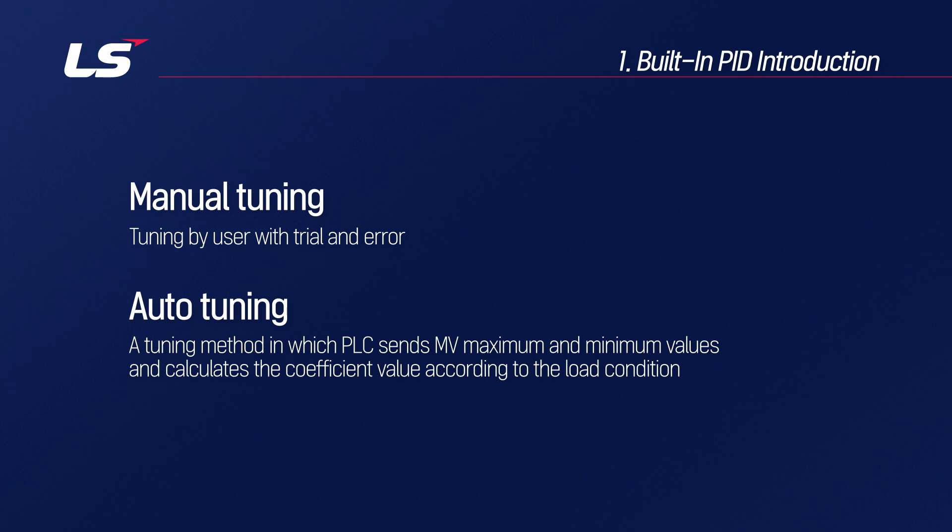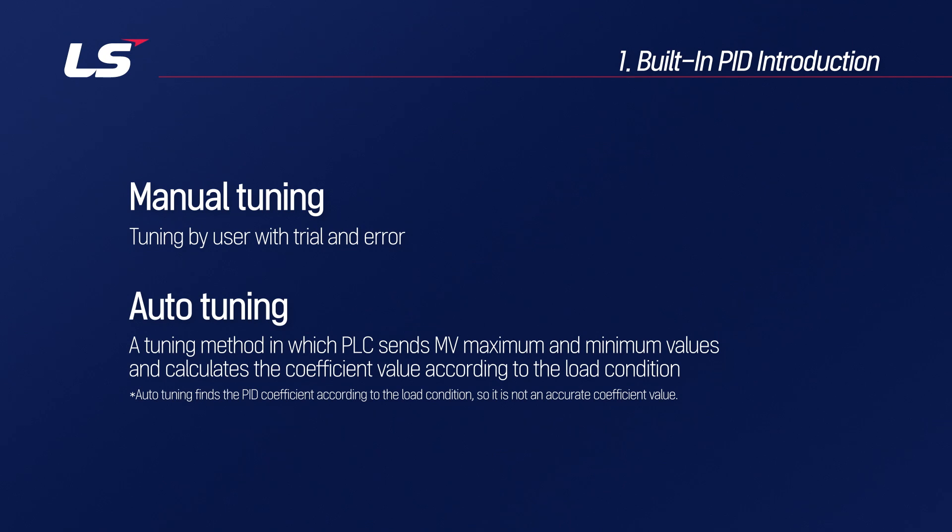There is a manual tuning in which the user puts in the values directly, and an automatic tuning method in which the coefficient value is calculated according to the load condition by sending the MV maximum and minimum values from the PLC. Auto tuning is an approximation according to the load condition, and it is not an accurate coefficient value.